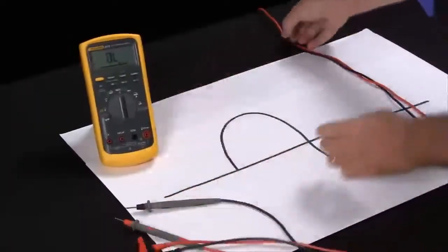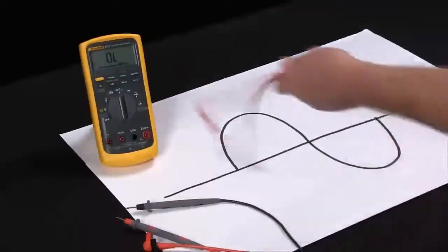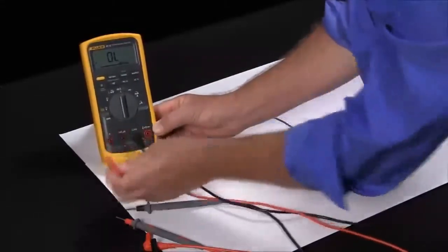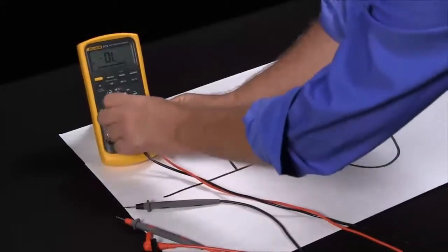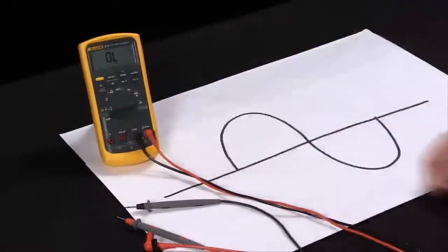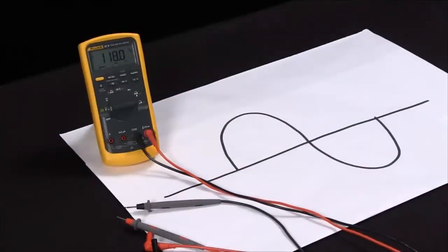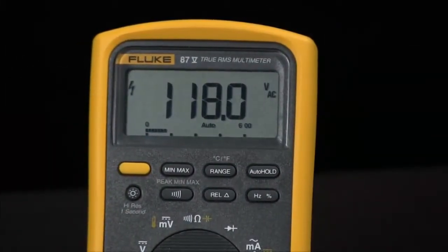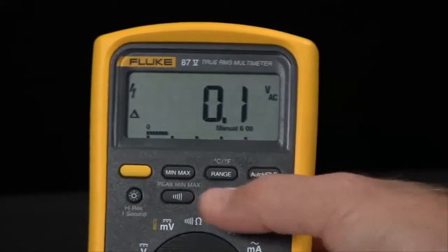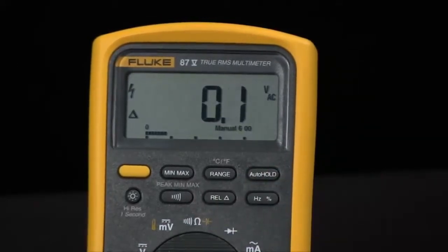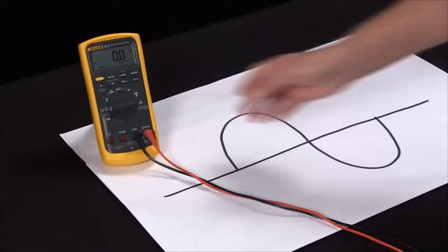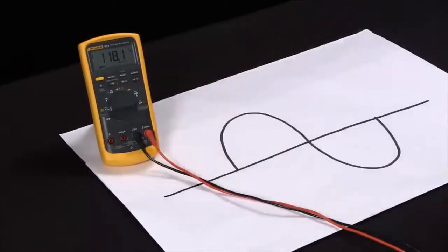This function, though, can be combined with several other functions within the Fluke-87 to help you troubleshoot some more complex problems. I'm just going to plug in, go to our sine wave. So here we have a 117 volt sine wave. So if I was going to go to the source and then hit the relative, that goes to 0. If I now went out to the load and saw minus 10 volts, I would know I would have a voltage drop. But this, as I said, this function can be combined with a couple other ones.